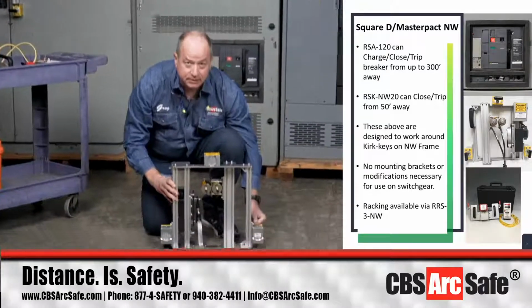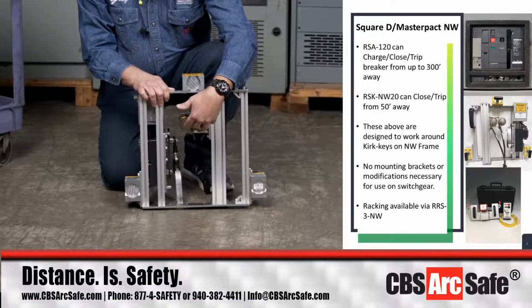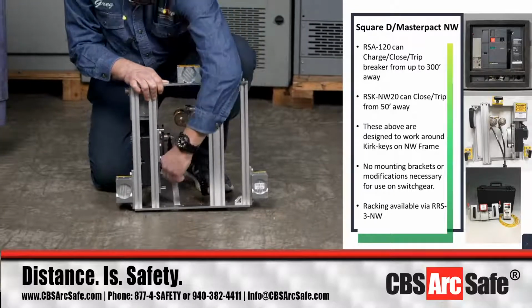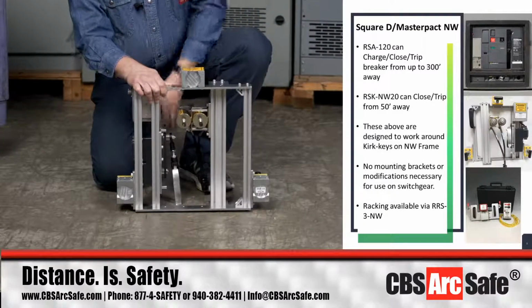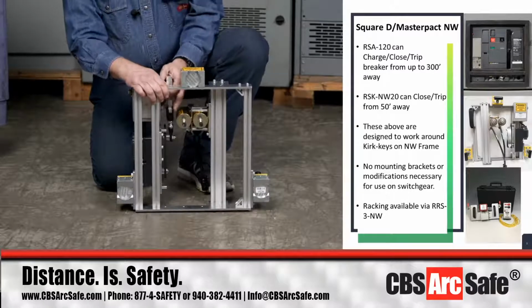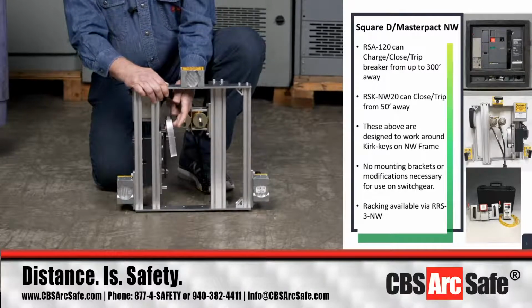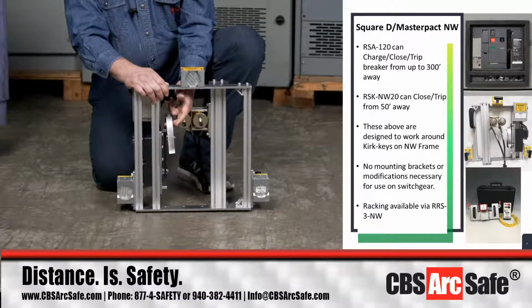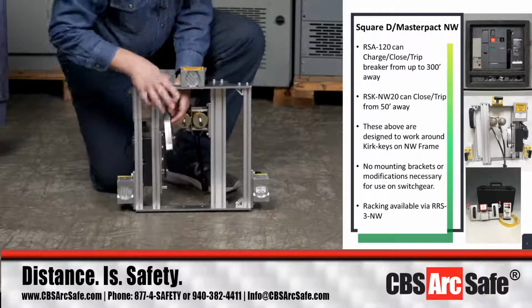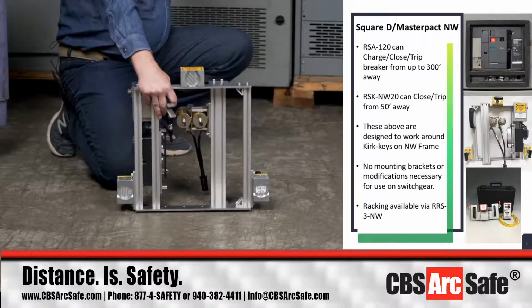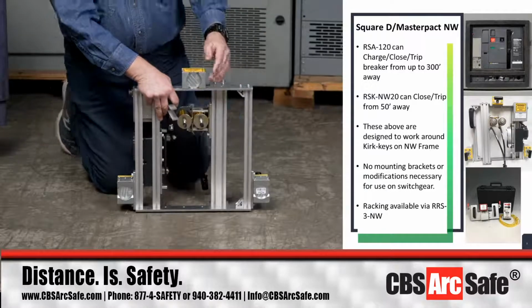On this side, we see the solenoids for closing and tripping, and we also see the handle. The handle is attached with an IGUS connector, and we will remove the handle and put it on the circuit breaker first before we place the rest of the RSA on there. Once we place the RSA on there, you can see that this is going to locate around our plastic escutcheon here to make it easy for setting up.